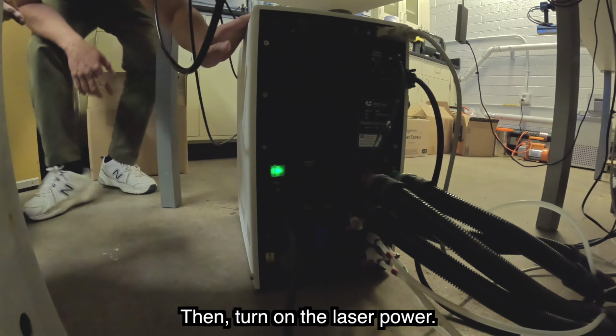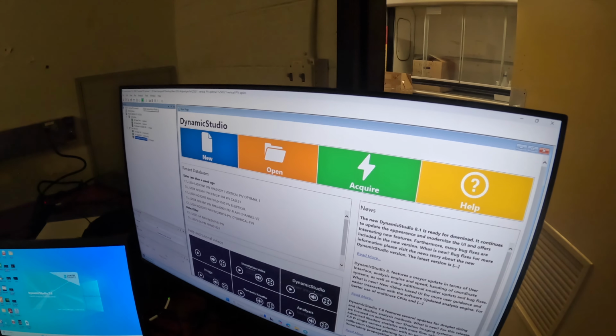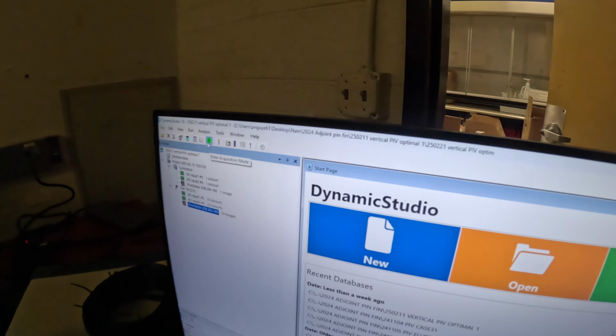Then, press the green button to open the shutter. Listen for the distinct sound. Create a folder following the naming convention. Now, we turn on the Dantec Dynamics software to run the preview. Then, click the Data Acquisition mode. Now we will run the preview mode. But make sure to check the synchronizer is activated. And these two numbers must always be positive.